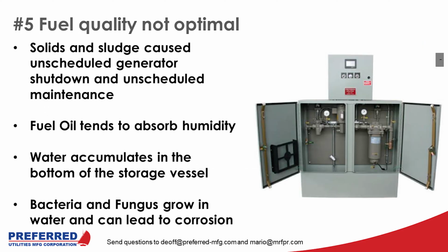Number five on our list is fuel quality. In many cases, we found that it was not optimal. Many tanks had solids, they had sludge that caused unscheduled generator shutdowns, and then engine maintenance just became a frequent task. Most end users had some type of inline strainer, but in some cases, these devices would just get clogged frequently, and the end users had to intervene. So, in general, most sites lacked adequate filtering and polishing for large quantities of fuel stored on their sites.